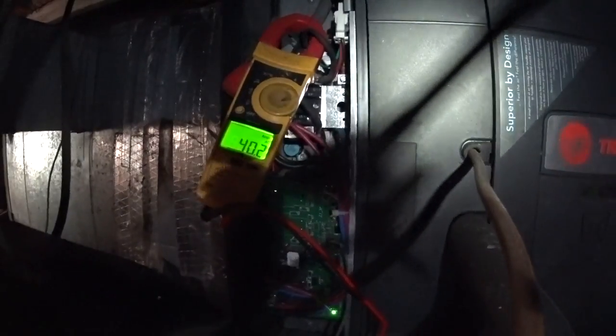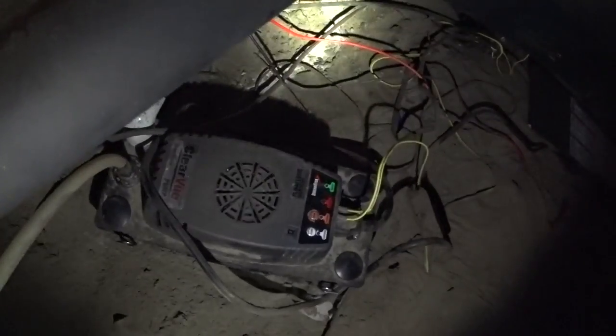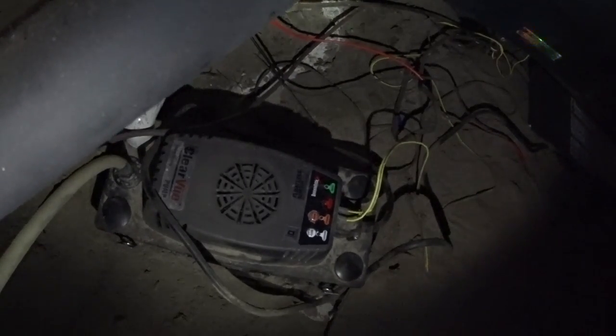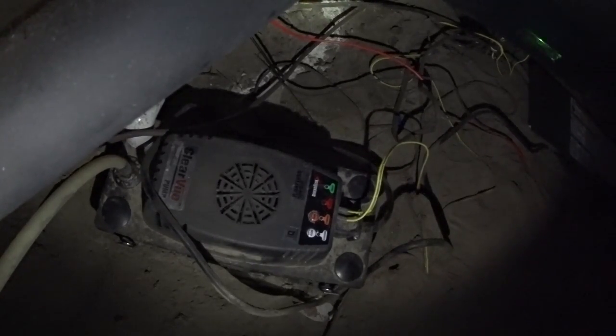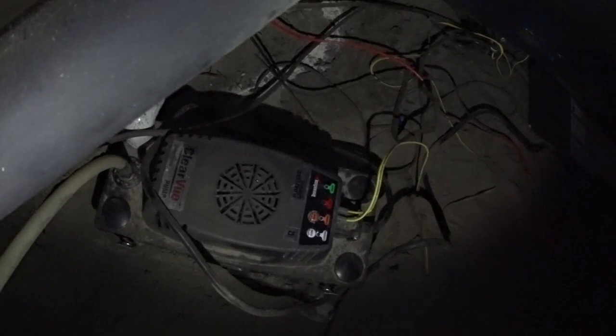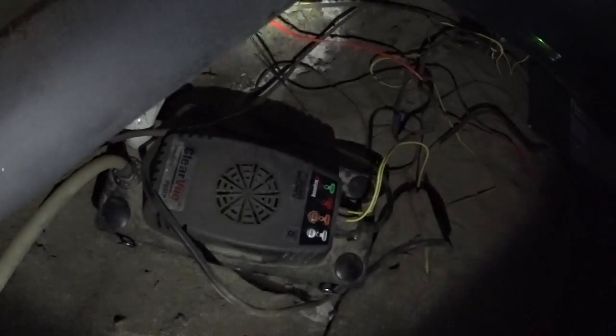I'm going on assumption here, but I would imagine that previously it dropped all of the heat strips in at one time rather than staging them. We do have a separate issue with this condensate pump. We have had trouble with these pumps. The floatless sensor will read that it's tripped when it's not. This one may be just a matter of garbage in the bottom of the pump, so I'll pull it out and clean out the reservoir and put it back in a little bit better level.